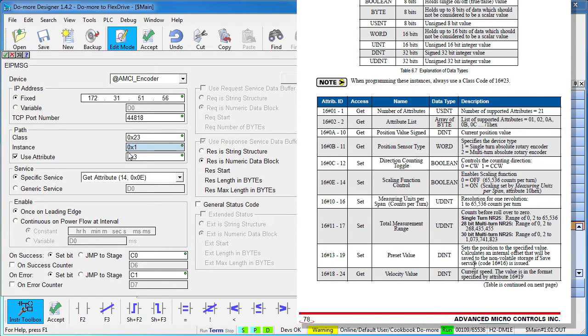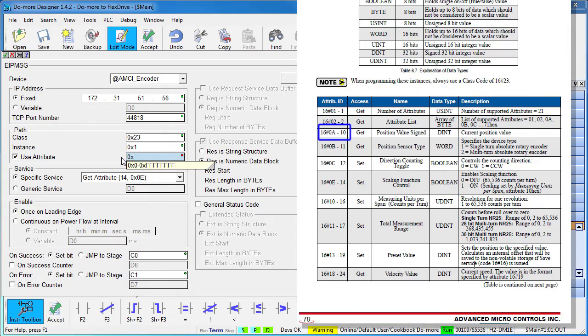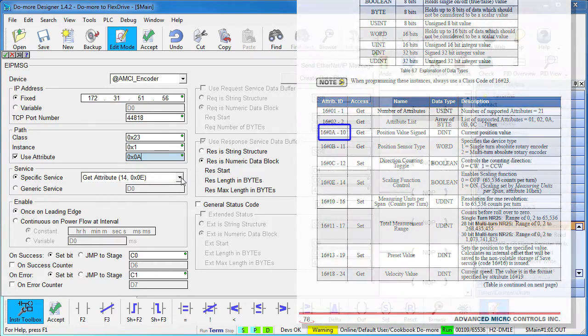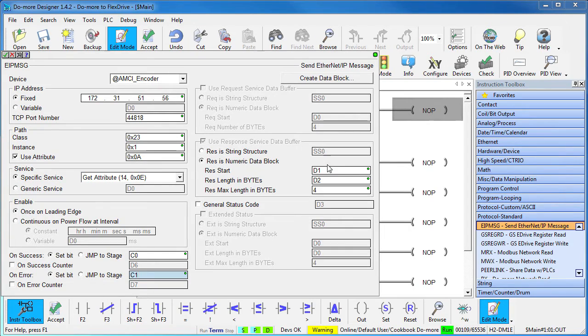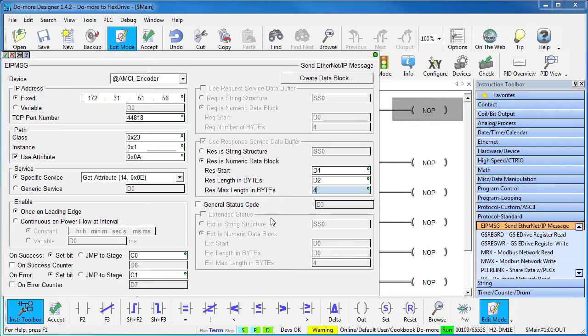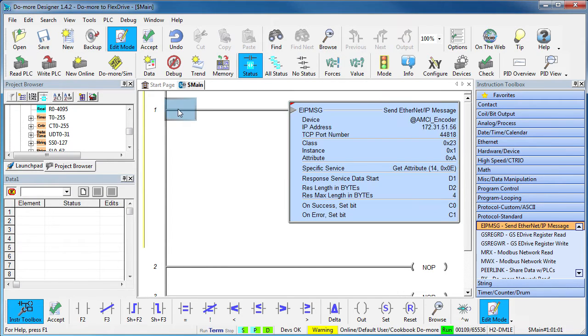And now we just pick which parameter or attribute we want. How about the current position, which is attribute 0A hex or 10 decimal and that goes here. We'll use these for our status bits and D1 for the result and D2 for the number of bytes received. The value is a dint which Appendix tells us is 32 bits or 4 bytes of memory. So we'll put that here. That's it.